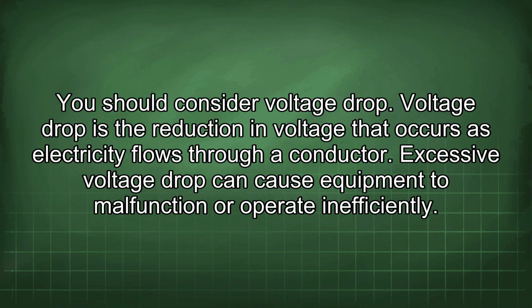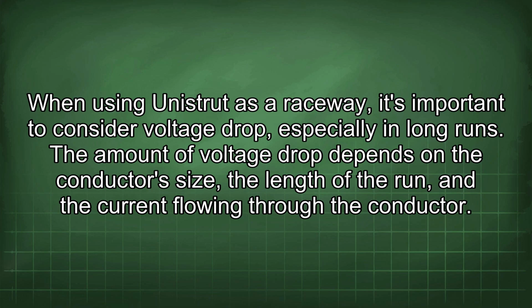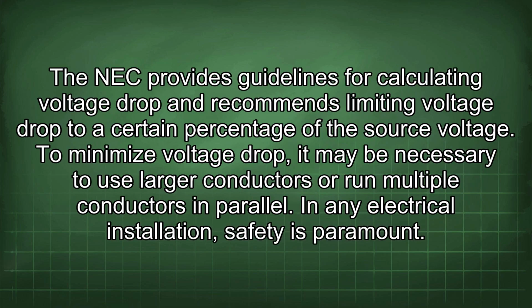Voltage drop is the reduction in voltage that occurs as electricity flows through a conductor. Excessive voltage drop can cause equipment to malfunction or operate inefficiently. When using Unistrut as a raceway, it's important to consider voltage drop, especially in long runs. The amount of voltage drop depends on the conductor size, the length of the run, and the current flowing through the conductor. The NEC provides guidelines for calculating voltage drop and recommends limiting voltage drop to a certain percentage of the source voltage. To minimize voltage drop, it may be necessary to use larger conductors or run multiple conductors in parallel.